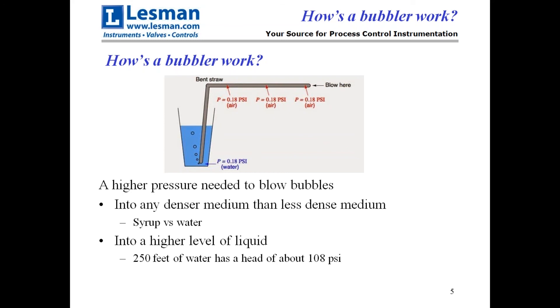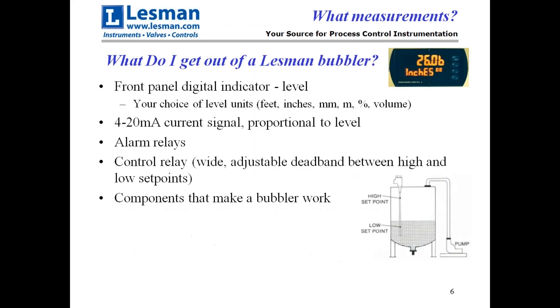If you install a bubbler, what do you get out of it? There's a front panel indicator that shows you level with units — inches, feet, or millimeters. You get a 4 to 20 milliamp signal out that's proportional to level. There are also alarm relays, or if you want to configure it that way, a control relay with wide-adjustable deadband so you can do pump-up or pump-down applications, plus all the other components like the constant flow regulator that actually make a bubbler work.